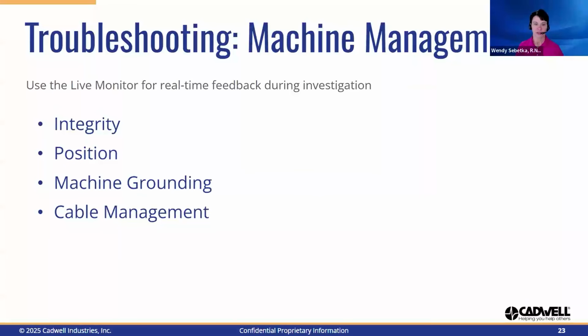When troubleshooting issues, it is important to have confidence in your machine. Routine maintenance and proper care will ensure system integrity and provide you with this reliance. We have discussed that having electrical devices near your system can be a source of noise, but we also need to consider that our device itself is an electrical source. Having your amplifier too close to your base unit or your power cord draped over your amplifier is directly exposing the device to electrical potentials that will likely introduce excessive signals.